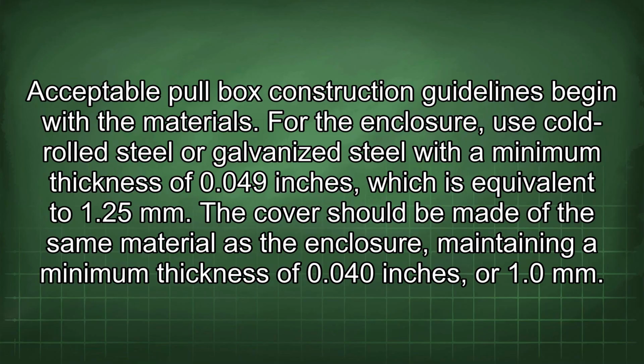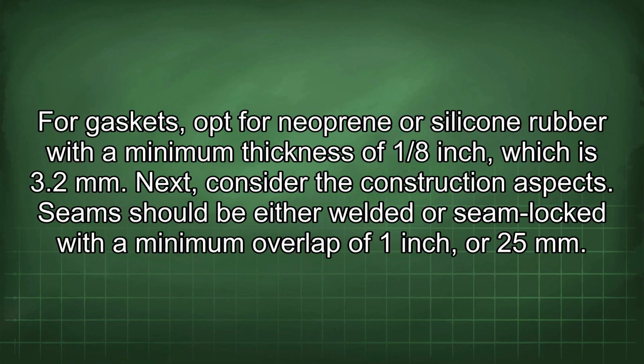Acceptable pull box construction guidelines begin with the materials. For the enclosure, use cold-rolled steel or galvanized steel with a minimum thickness of 0.049 inches, which is equivalent to 1.25 mm. The cover should be made of the same material as the enclosure, maintaining a minimum thickness of 0.040 inches or 1.0 mm. For gaskets, opt for neoprene or silicone rubber with a minimum thickness of 1/8 inch, which is 3.2 mm. Next, consider the construction aspects.